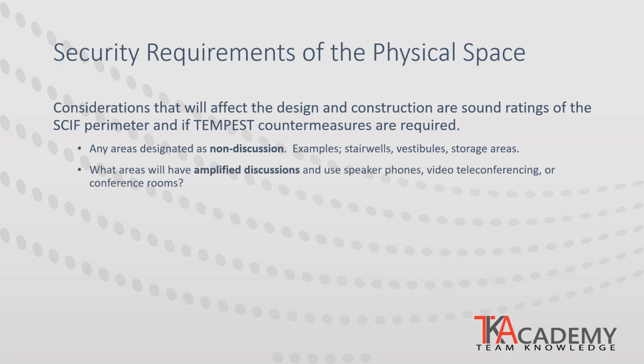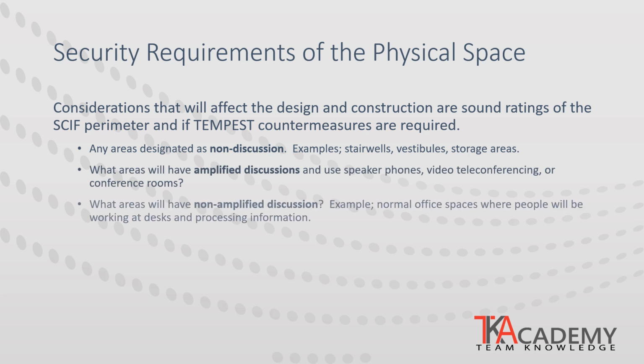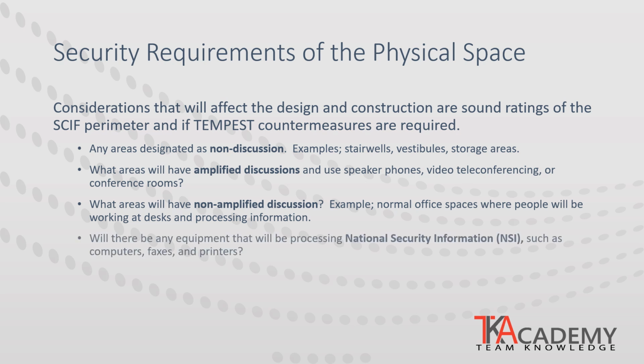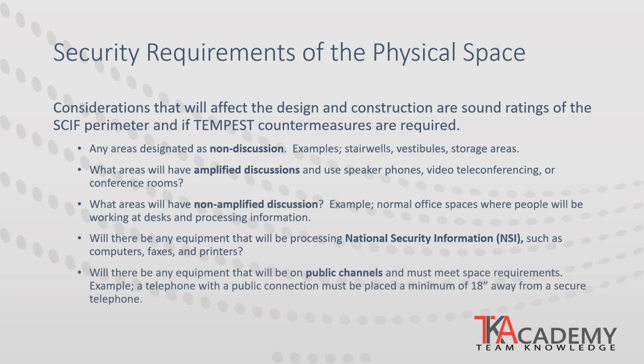What areas will have amplified discussions with the use of speakerphones and video conferencing? Which areas will have non-amplified discussion, such as normal office working areas? Will everyone who works within the SCIF have equal access to secure equipment? Equipment that will be on public channels or networks must meet minimum distancing requirements, such as a standard telephone must be kept at a minimum of 18 inches away from a secure telephone.